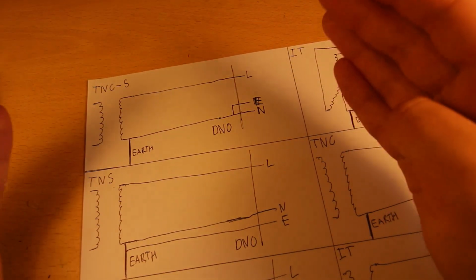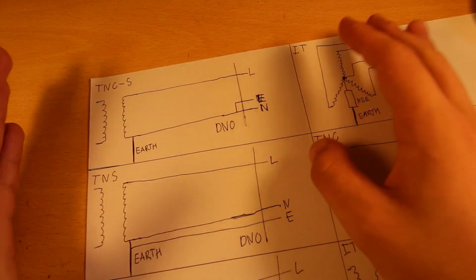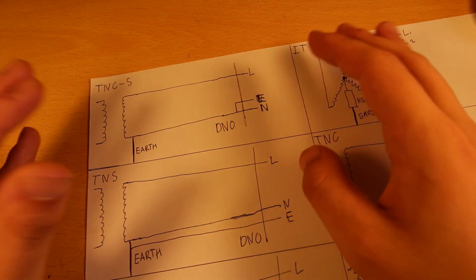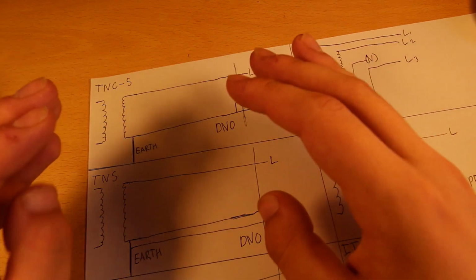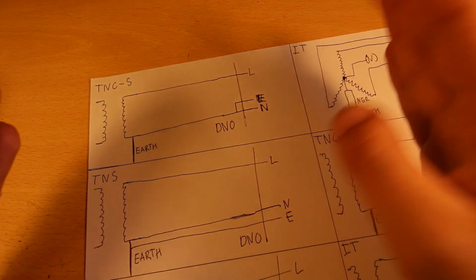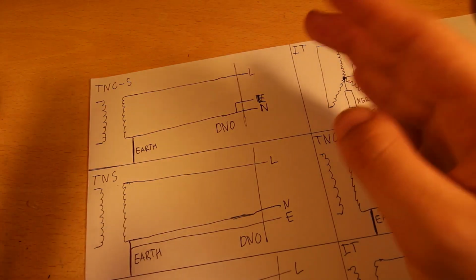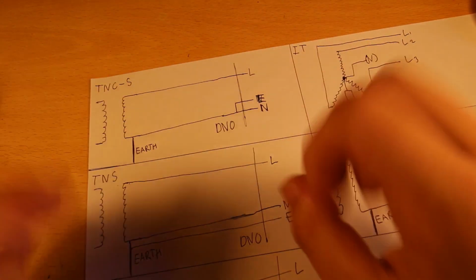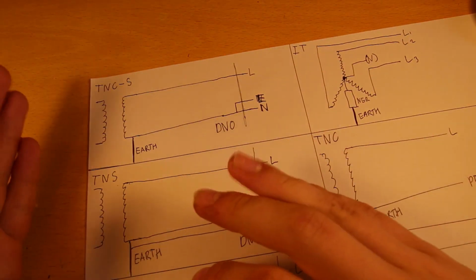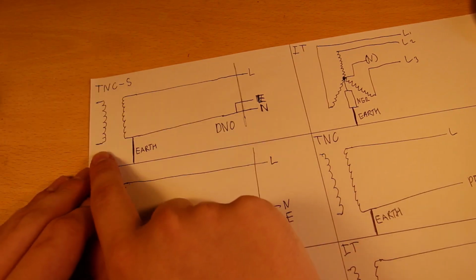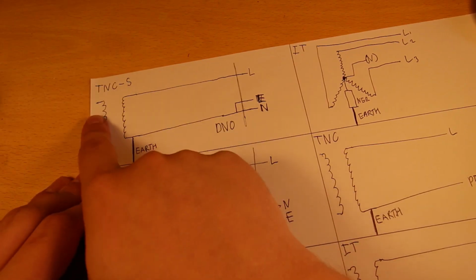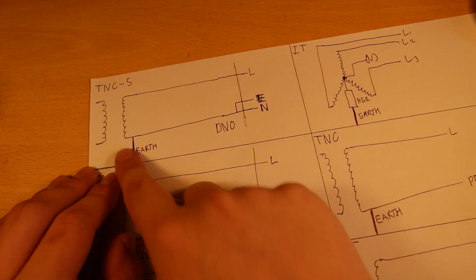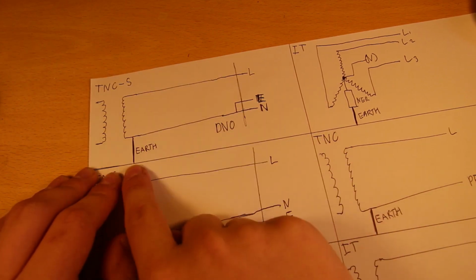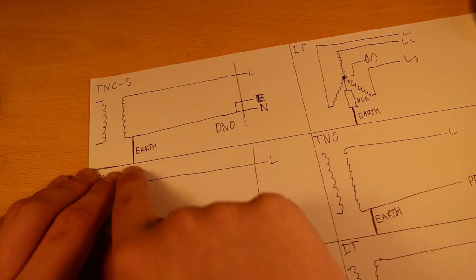So first one we have is TNC-S. This is by far the most common earthing system in the UK, and it is also the most dangerous and I would argue the stupidest, because of the PEN fault issues, but we'll get onto that in a second. But what happens is you have your transformer where the 11 kV comes in. The secondary winding is earthed by the supplier at the transformer.